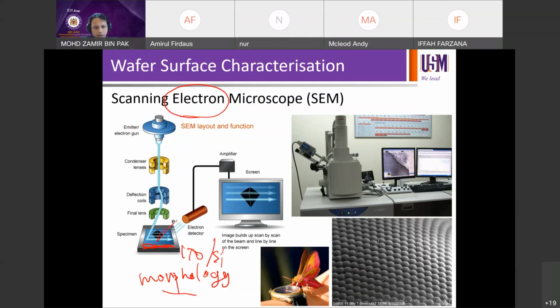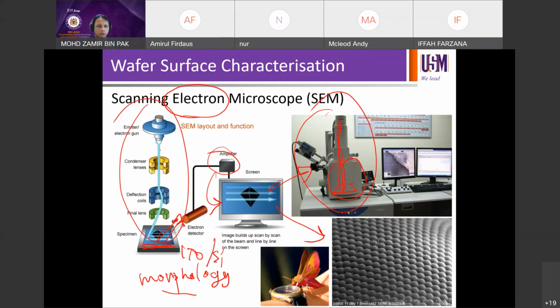Then the information will be deflected and detected by the detector, amplified, and transferred into an image, and then you can see this image. This is how it looks as a system, the whole setup that we're talking about here. And this is the chamber where you normally put your sample. Say your sample, ITO on silicon, is there: the beam comes from the top through all the parts in between to get focused on the sample, and then it's detected by the detector and reported as an image. Then you see the morphology of, say, ITO on silicon. Those are the controllers, to control focus, magnification, current, voltage and so on, to get a clear image.